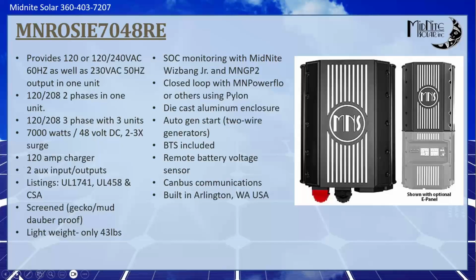It's very lightweight. The thing weighs about 43 pounds. It is screened so that bugs and insects and stuff don't get into it. It is not outdoor rated. The Rosie, like all of the rest of the Midnite Solar products, except for the all-in-one and the PowerFlow 16, are indoor rated. It is listed UL 1741. The mobile version is UL 458, and they are both listed for Canada as well, CSA listed.